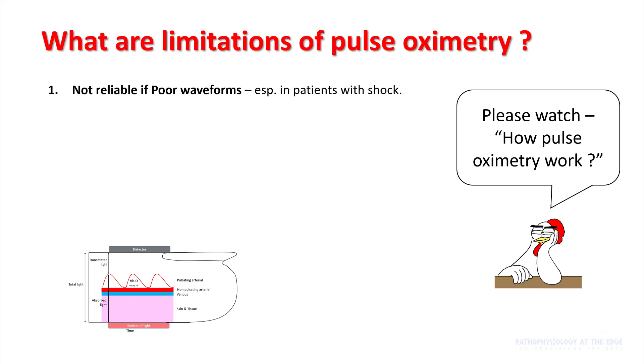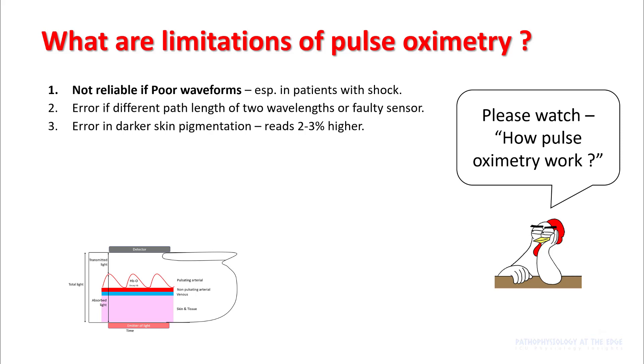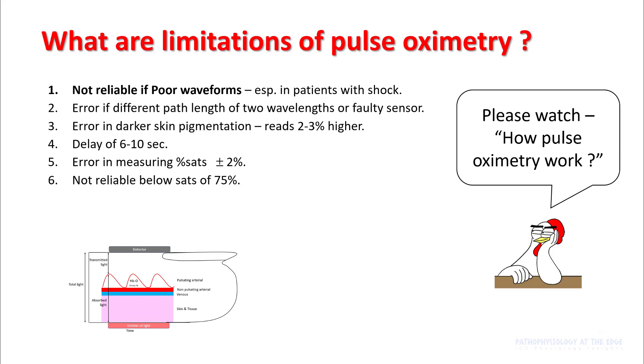A major limitation of pulse oximetry is that readings are not reliable if you have a poor waveform, for example in a patient with shock or hypotension. There can be error if you have a faulty sensor or different path lengths of the two wavelengths. You can get error rates with darker skin pigmentation. There is a delay of 6 to 10 seconds before measurement, an error rate of around 2%, and readings are not reliable below SaO2 of 75% or hemoglobin less than 5 grams.